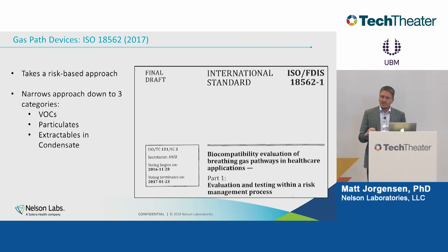So what this standard is all about is taking a gas path device, running it or simulating clinical use, and actually measuring the volatile organics that come out in the gas, measuring the particulates that come out in the gas, and if there's a chance that liquid could collect in the device and run into the patient, then also doing some extraction and analysis of those liquids. I think it's a standard that makes a lot of sense. I love that it's out there, and it can really save you a lot of time and money if you have one of these types of devices.